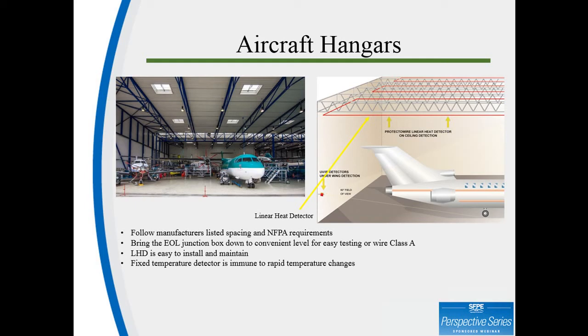Alternatively, the designer or installer may want to consider wiring in a Class A configuration, allowing the system testing and inspections to be completed back at the control panel. This is another ideal application for the CTI series detector, as hangars can be protected by high expansion foam systems, and you want to be 100% sure there is a fire or a hotspot prior to discharging a suppression system within a hangar.